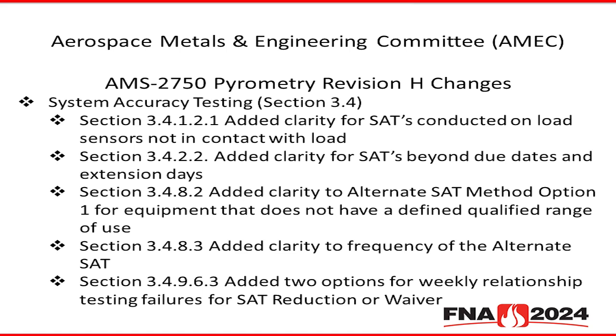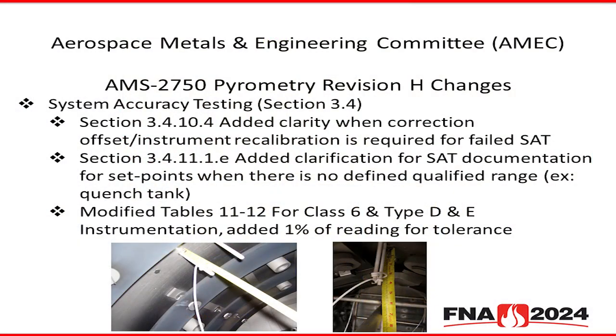We talked about beyond due dates and extension days, and the alternate SAT method for those that don't have a defined qualified range of use, like quench tank freezers. More clarity on the frequency of alternate SATs. We added two options for the weekly relationship testing failures for SAT reduction or waiver. More clarification in 3.4.10.4 about when correction offsets or instrument recalibration is required due to a failed SAT. Added clarification for SAT documentation for set points when no defined range is used.